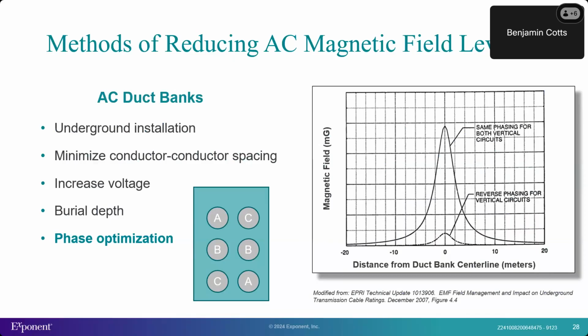Other things that can decrease magnetic field levels are increasing the voltage, because for the same amount of power transmitted, a higher voltage leads to a lower current and hence a lower magnetic field. You can also increase the burial depth, which has more effect directly above the line but won't have as much effect, say 25 or 50 feet away, as it does directly above.